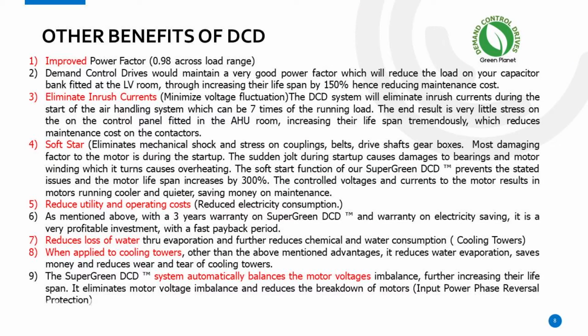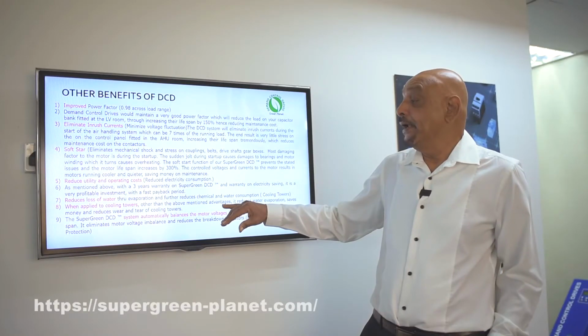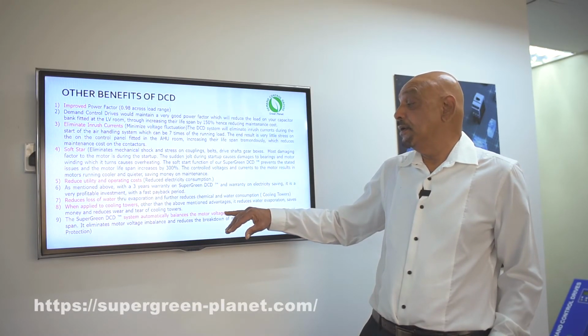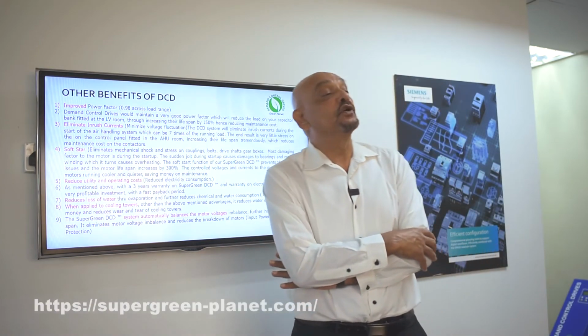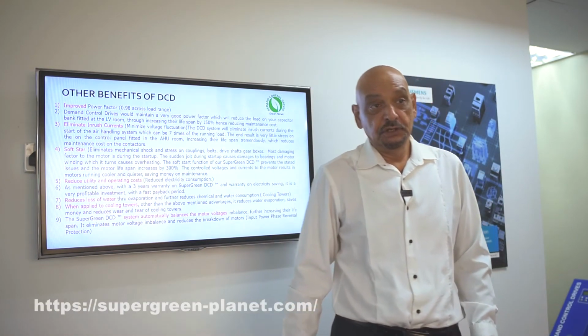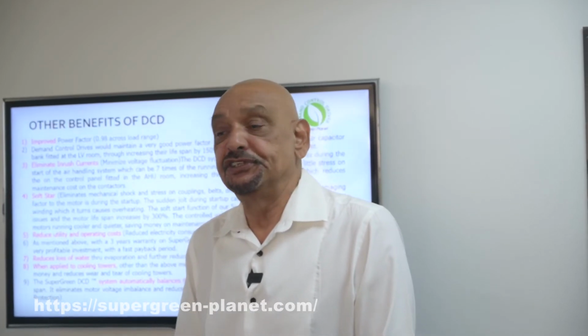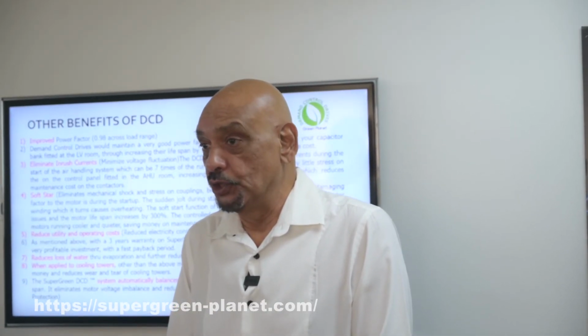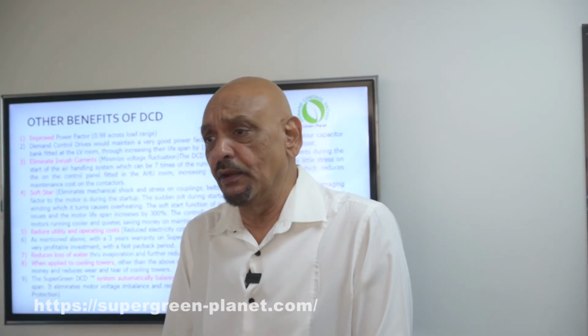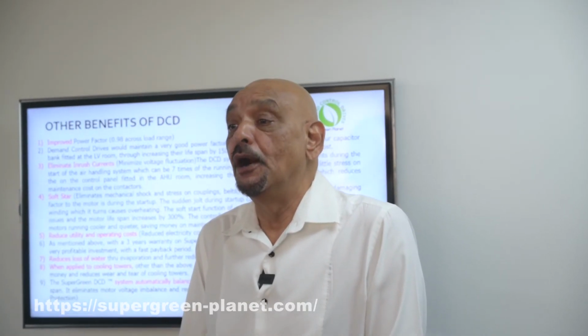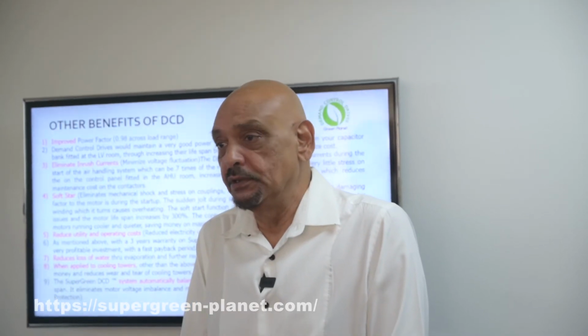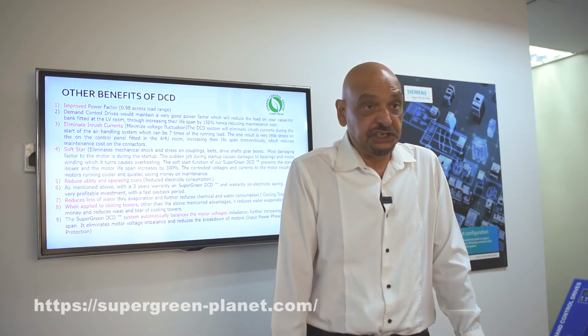Reduce utility and operating costs. As I said, you're going to reduce your energy consumption, and it's going to be reflected on your electricity bill at the end of the month. Then apart from that, the system will automatically, for example, balance the voltage, which is channeled out to your motor. Apart from that, what else are you going to get? There is a motor protection system which is built into the system, into our DCD itself.